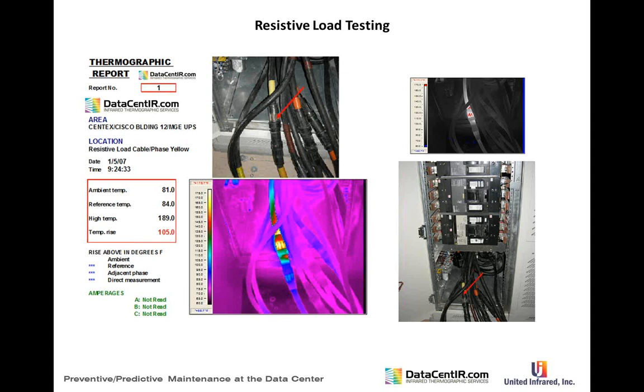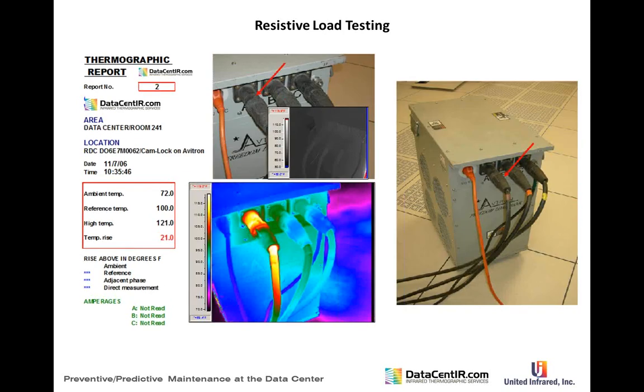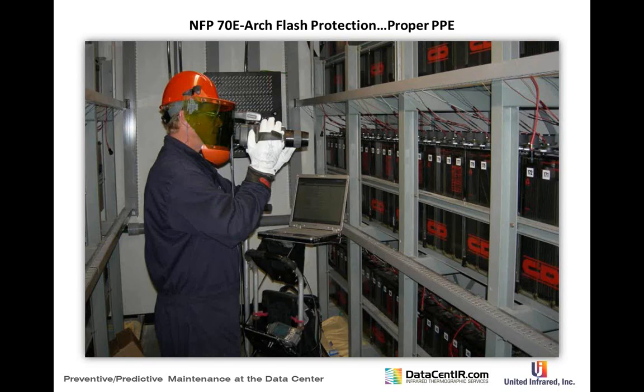In some cases the test must be postponed if cables can't safely supply the load. A small resistive load testing unit for PDUs had a major problem — repaired by fixing the cam-lock connection in about an hour. We also document repaired items. This brings up NFPA 70E arc flash protection, which is required when checking electrical equipment.